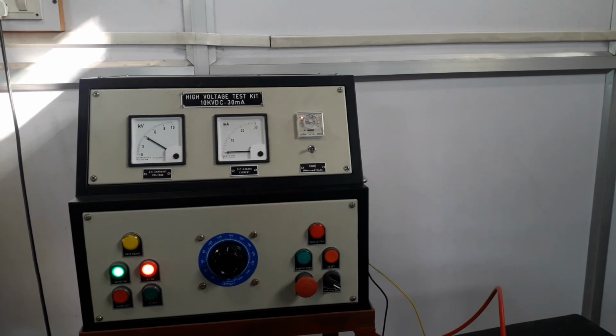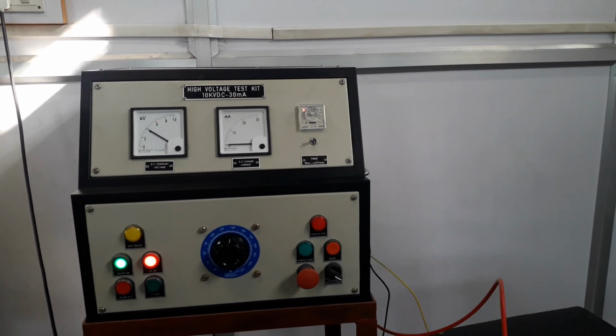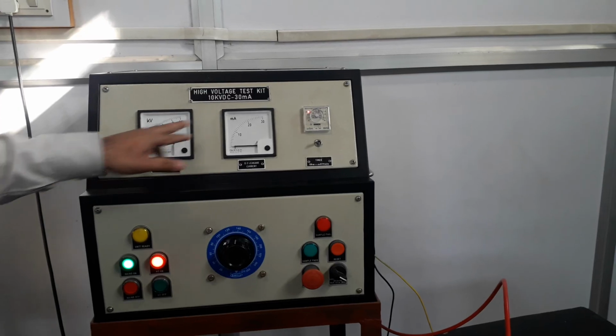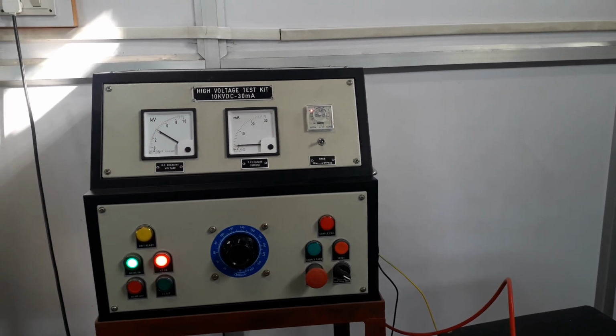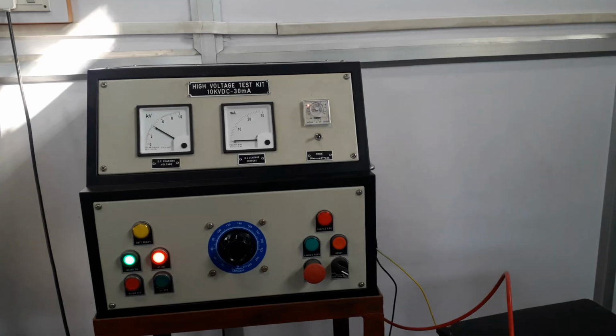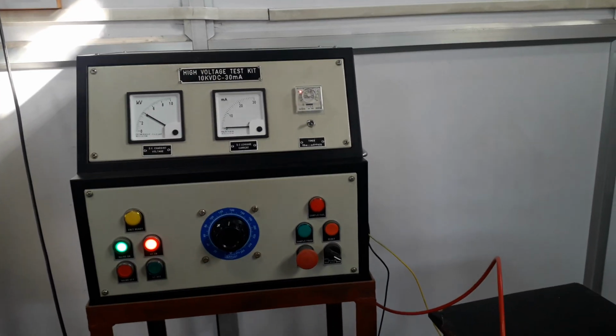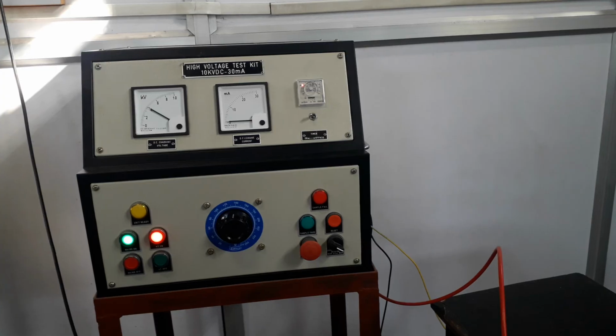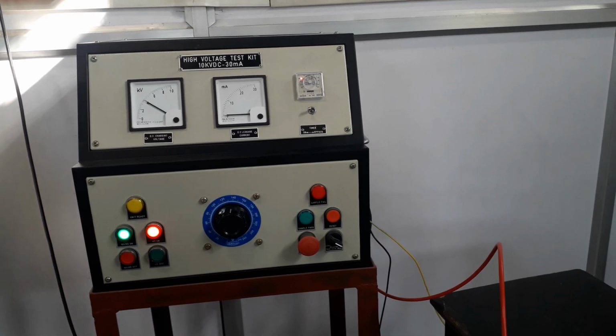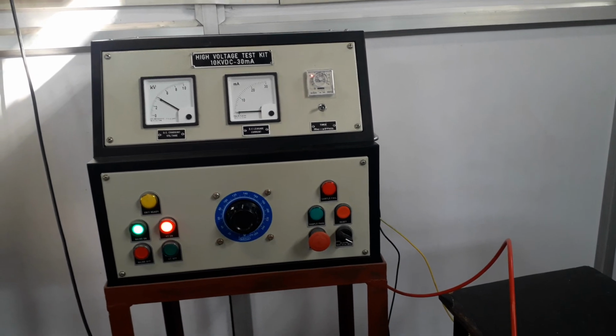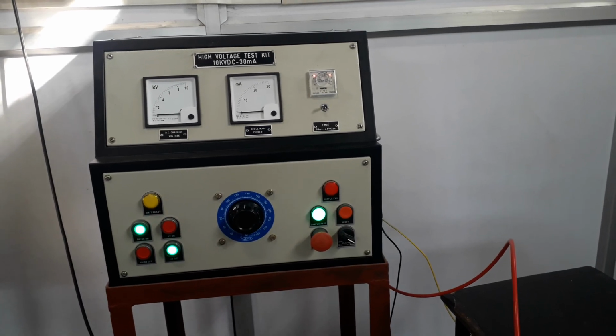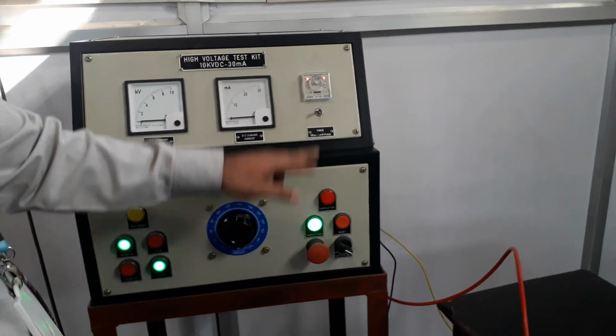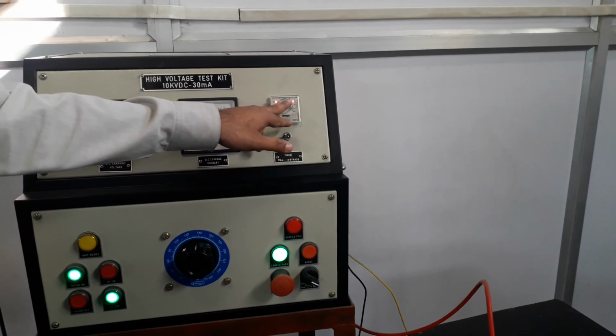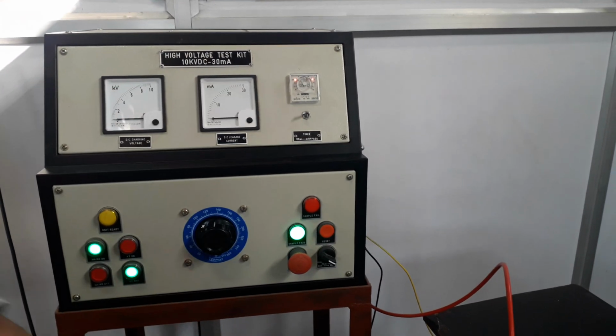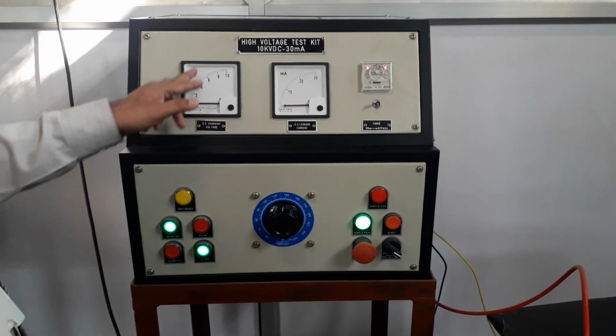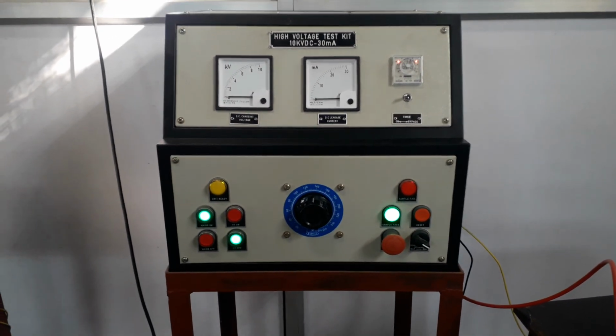So here you are able to see that high voltage is applied now, and simultaneously the timer is also on. After some time, if it fails, then the fail indication will glow. If it passes, then the pass indication will glow. Also, we have set the leakage current to the 30 milliampere maximum range. Okay. So you can see here that the sample has passed the test because it is able to withstand the particular voltage for the particular time, maybe 6 seconds, and after it passes, the voltage naturally decreases.